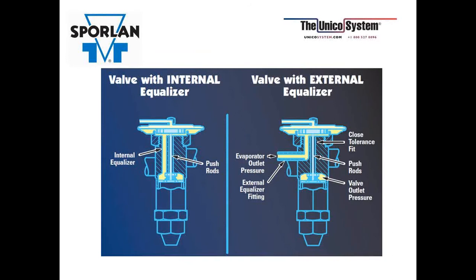Sporlan produces internal and external equalized TEVs. The internal equalized valve has a drilled passageway on the outlet side of the valve to the underside of the diaphragm. It senses the low side pressure at this point, and any additional pressure loss through the coil or distributor, if one is being used, will not be sensed. The external equalized valve has an extra connection that must be installed on the suction line downstream of the bulb location, and this will allow the valve to sense the actual true low side pressure at the suction line.